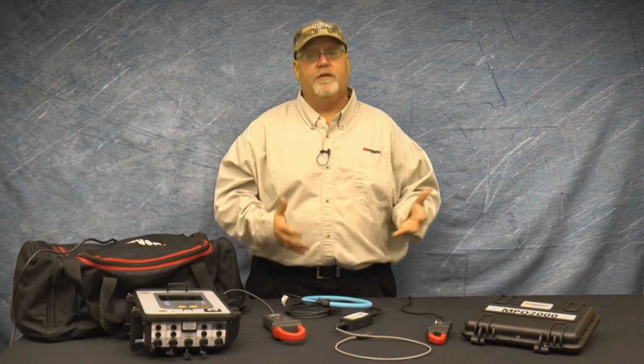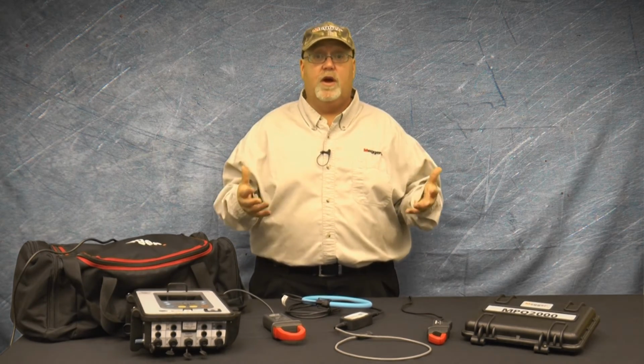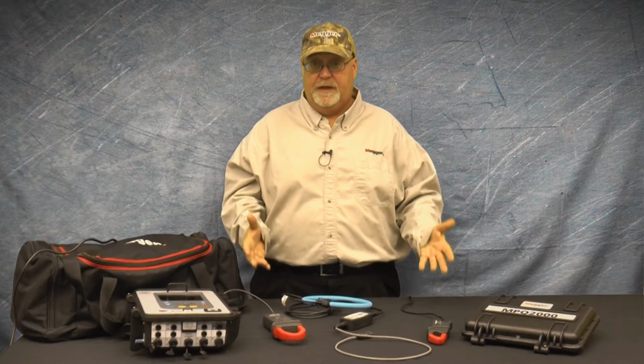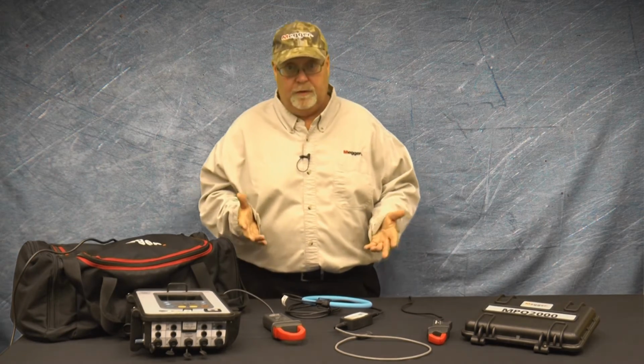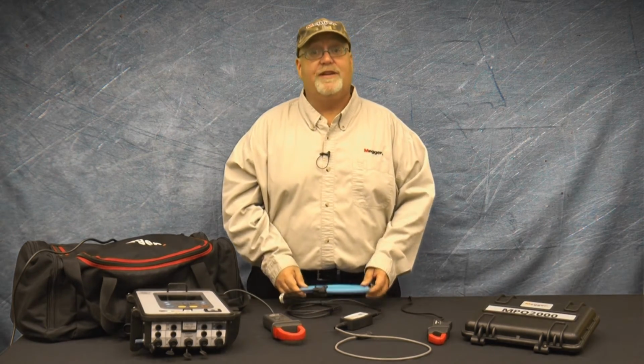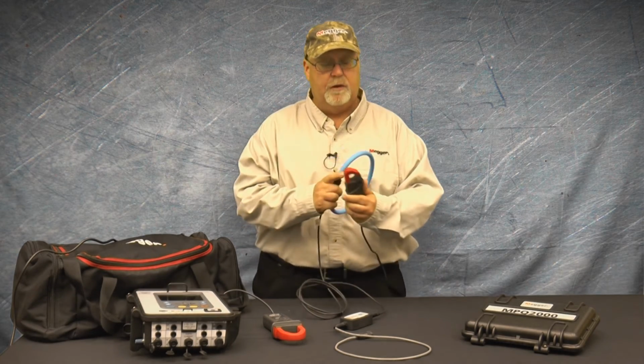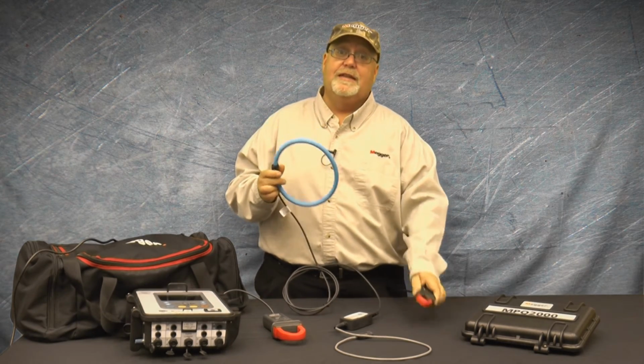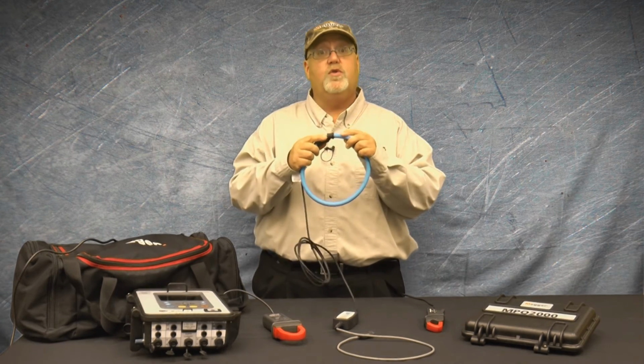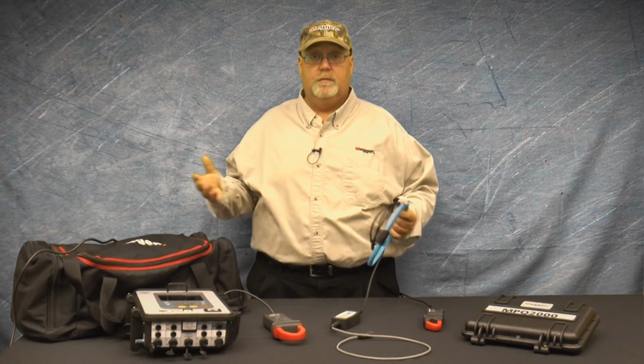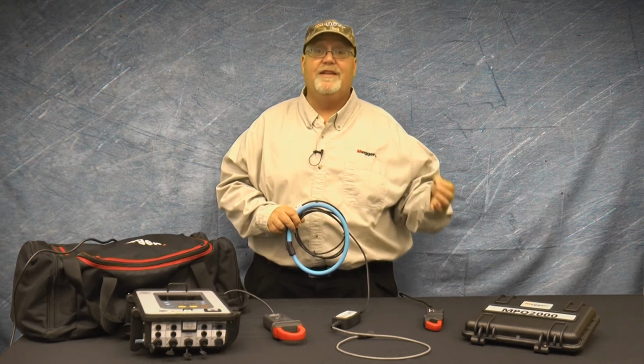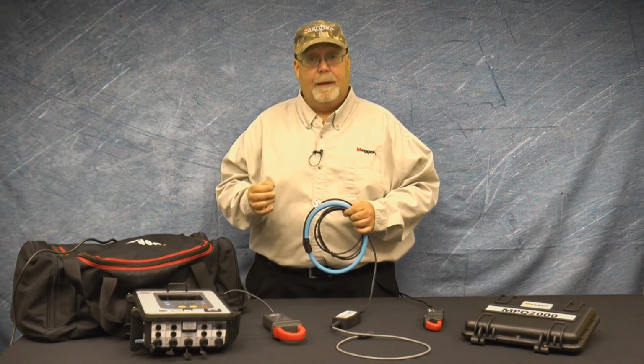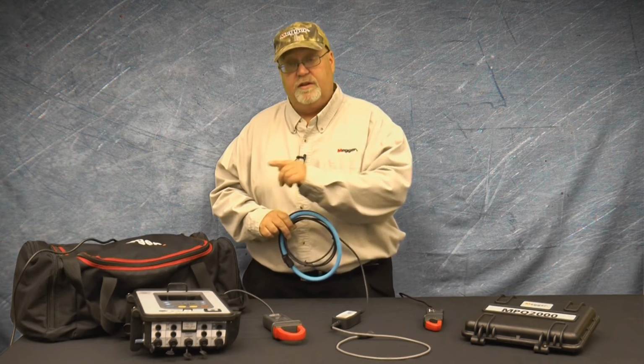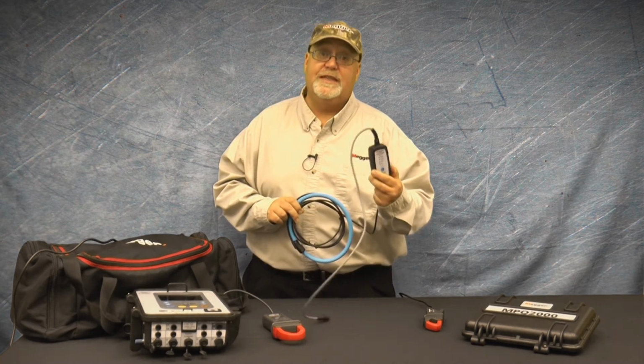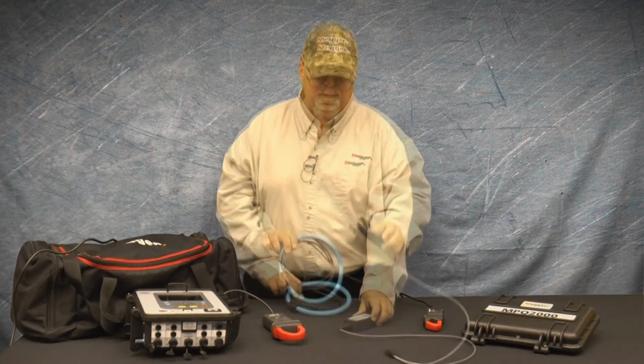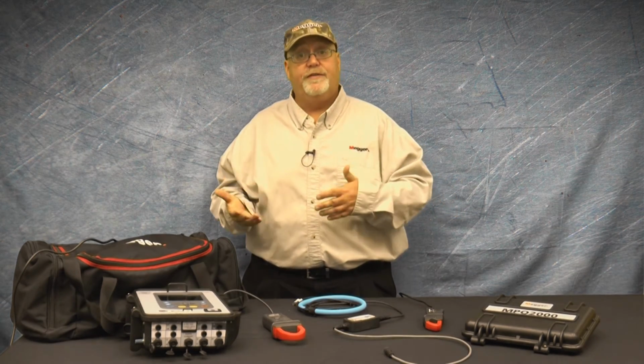Okay, so now we've seen our different types of current clamps. Now the question is, how do I know which one to pick for the application? Well, here's several steps to follow. First, you have to take the inner diameter of the CT into account. First and foremost, the CT has to be able to fit around what you want to measure. Step 2, is your application going to be indoor or outdoor? If your application's outdoor, not only does the unit need to be weatherproof, but the CT has to be weatherproof as well. Step 3, are you measuring AC or DC?